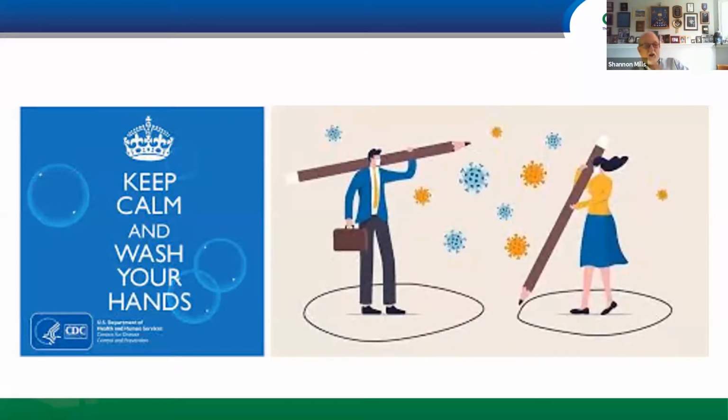And I'll just say, if you do it, dilute it 1 to 10 to 1 to 13, depending on the higher or lower concentration in the original bleach, no more than 10-minute contact time. And do it until you get the results you're looking for. Again, I'm not advocating it. You should follow the manufacturer's recommendation.